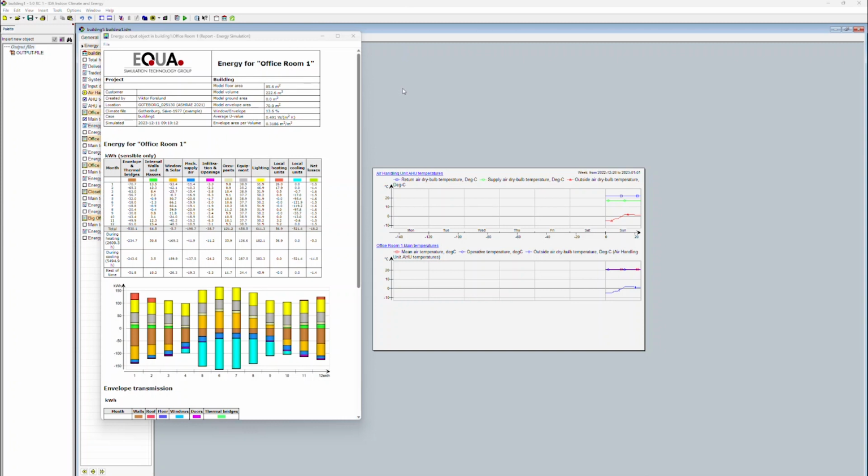This can, for example, be explained with solar gains that occur within a space at 3 o'clock in the afternoon. If heating requirements occur at 5 o'clock in the afternoon, the solar gains that were captured earlier will still have an impact on the requirements from the plant. The default definition is that casual gains or losses have an influence for up to 24 hours with a diminishing effect over time. This length can be changed under system parameters.